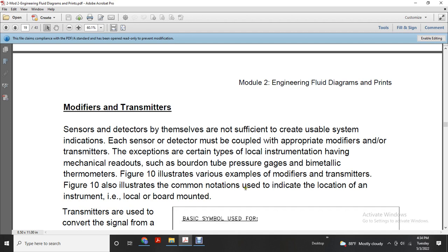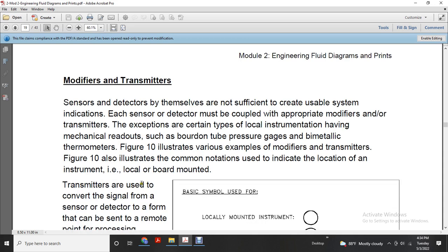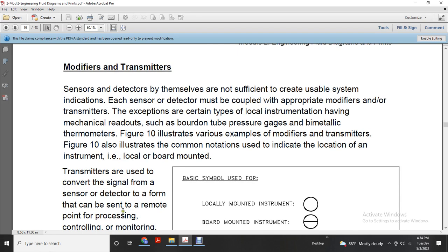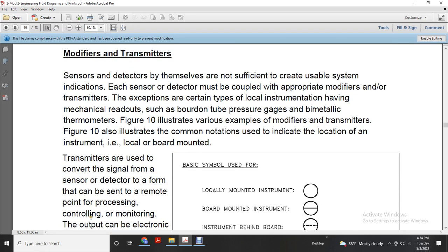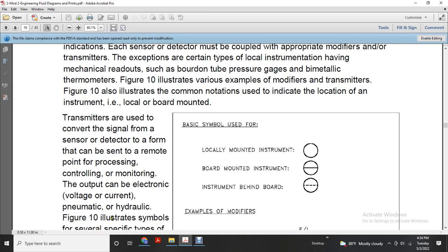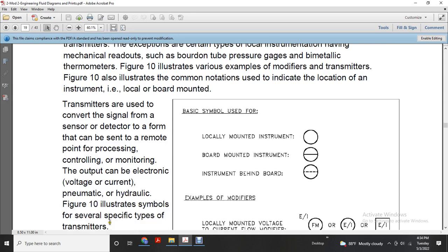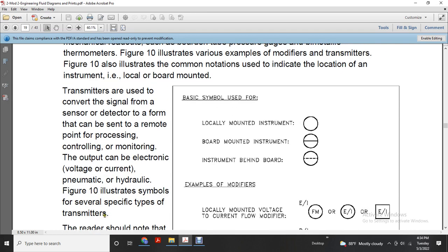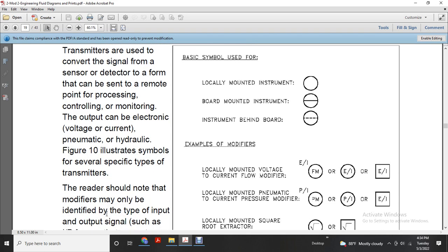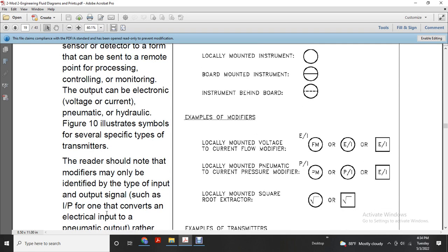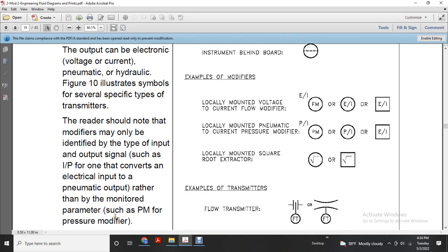Figure 10 also illustrates common notation indicating the location of the instrument: local, board mounted. For transmission, the signal from the sensor or detector must be in a form that can be sent to a remote point for processing, controlling, or monitoring. The mounting output could be electronic voltage or current, pneumatic, or hydraulic. Figure 10 illustrates the symbols of the specific types of transmitters. Readers should note that modifiers may only be identified by the type of input and output, such as I/P, which converts an electrical input to a pneumatic output, rather than being identified by the pressure parameter, such as PM for pressure modifier.